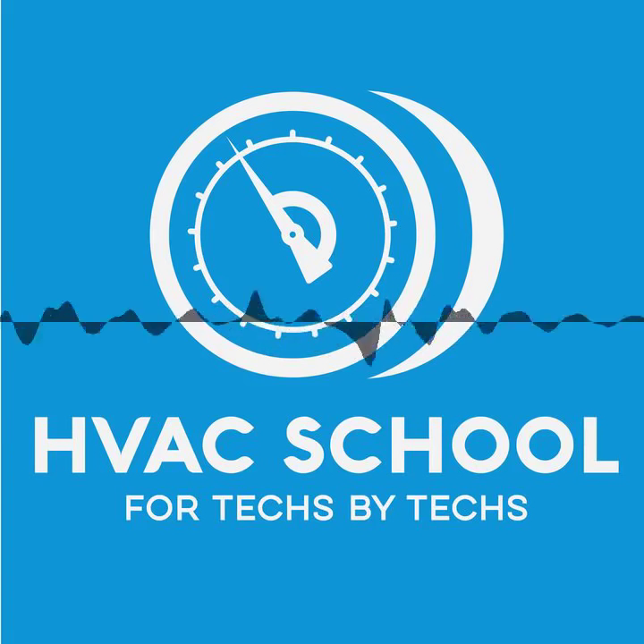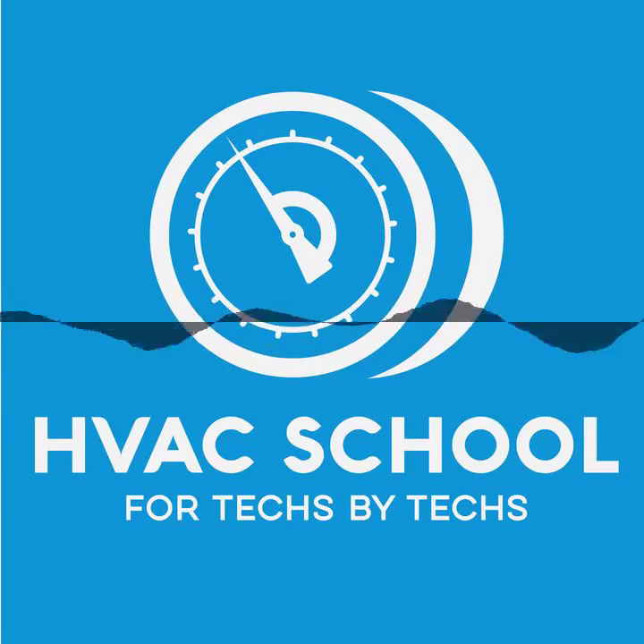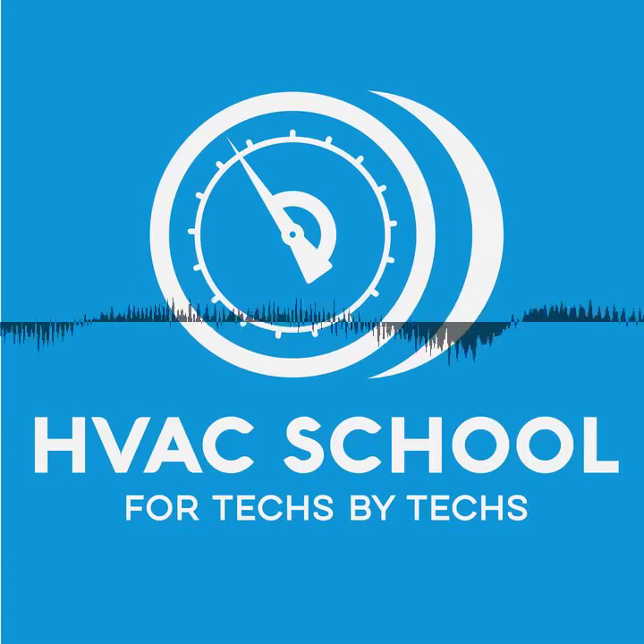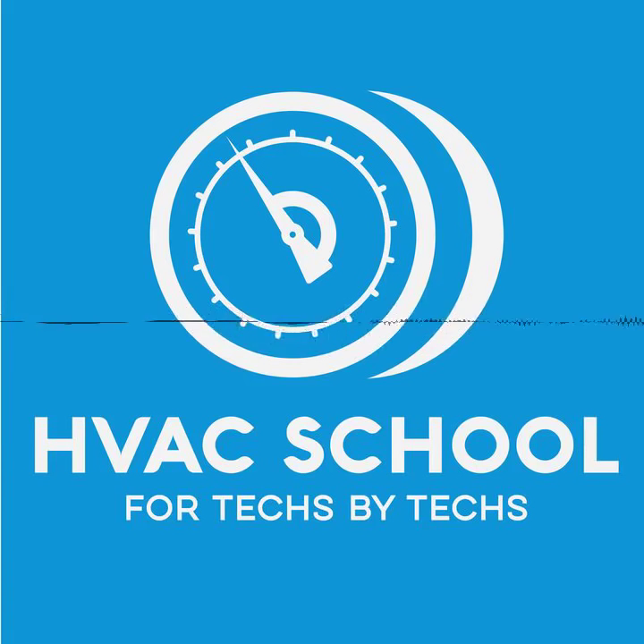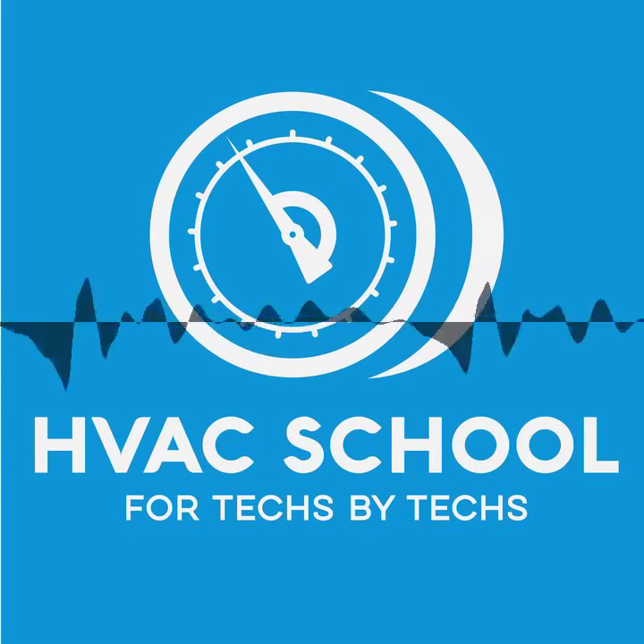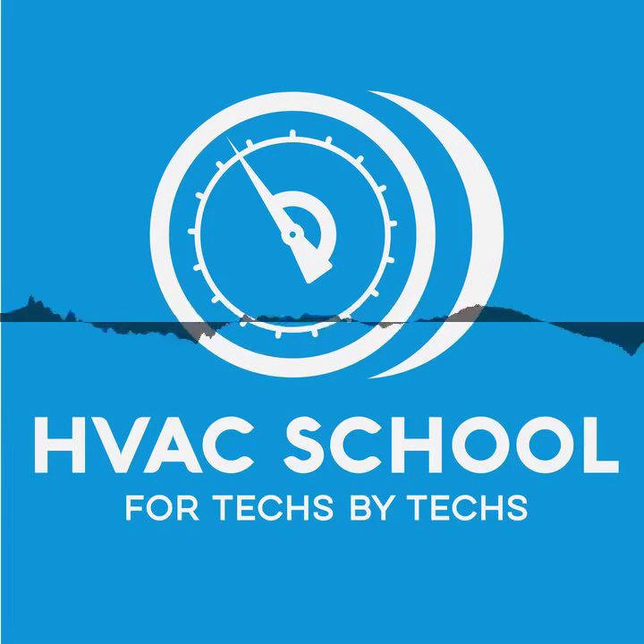Well, never fear. RectorSeal makes the Dissolve kit, and it's the word dissolve without the E on the end, as is very popular nowadays, to omit the vowel. So it's a dissolve, and it's a kit. It's also a cleaner, and so they have a cleaning solution that you can spray on the evaporator coil and blower wheel.